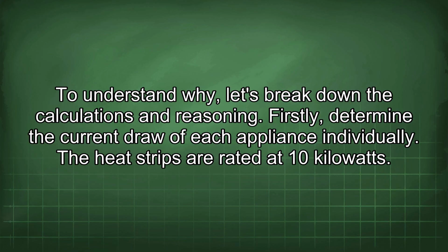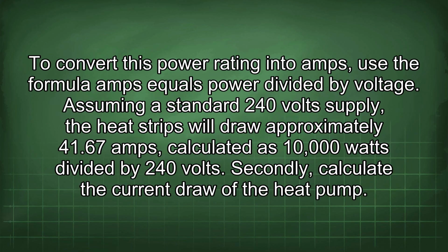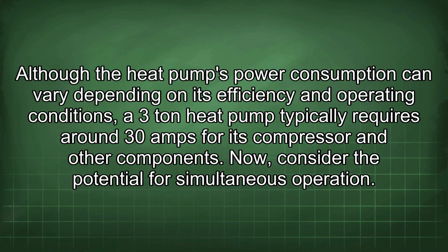Firstly, determine the current draw of each appliance individually. The heat strips are rated at 10 kilowatts. To convert this power rating into amps, use the formula amps equals power divided by voltage. Assuming a standard 240 volt supply, the heat strips will draw approximately 41.67 amps, calculated as 10,000 watts divided by 240 volts. Secondly, calculate the current draw of the heat pump. Although the heat pump's power consumption can vary depending on its efficiency and operating conditions, a 3-ton heat pump typically requires around 30 amps for its compressor and other components.